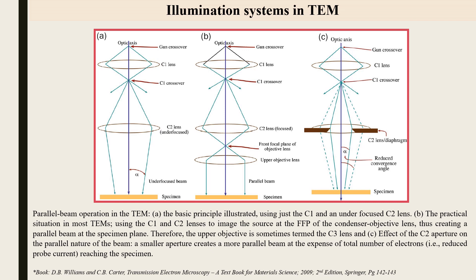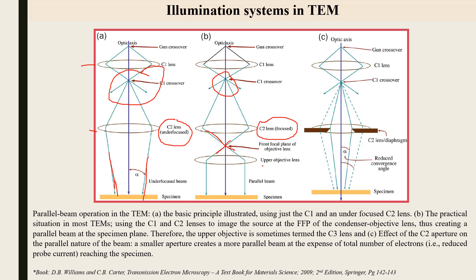Regarding the illumination system: in the first example, only C1 is used and C2 is under-focused, so there is no crossover at the correct image plane. In the second example, after C1 produces the first crossover, C2 is adjusted to get a focused beam with a second crossover at the front focal plane of the objective lens, resulting in a parallel beam toward the specimen.